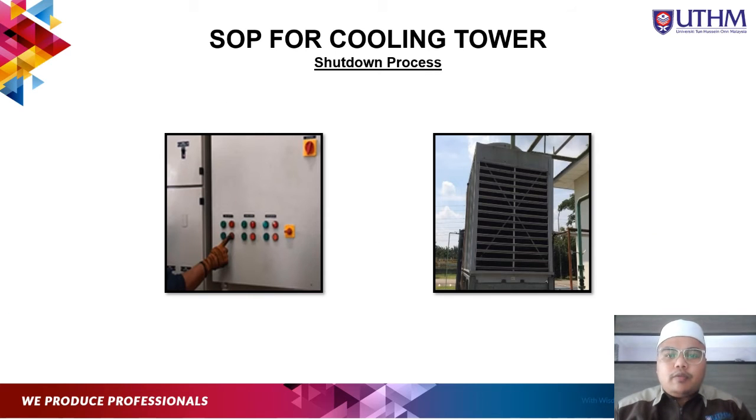For the shutdown process of the cooling tower, first switch off the discharge and suction pump and also the cooling tower fan at the switch panel. Then make sure all the valves on the lines related to the cooling tower are fully closed or isolated, as we call it, and the drain is open.